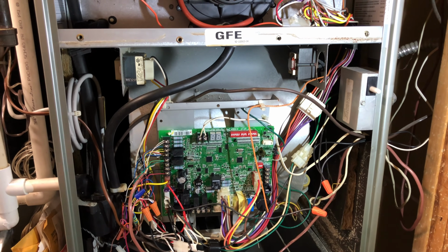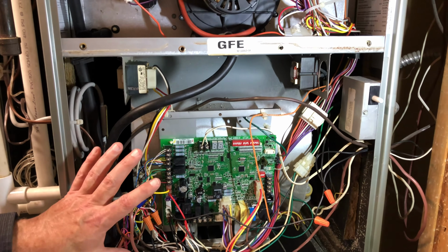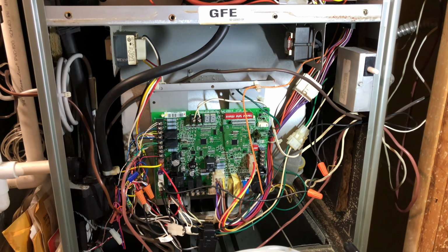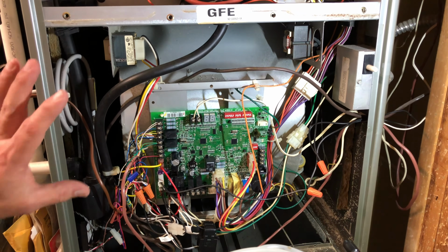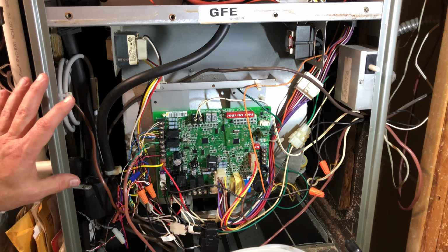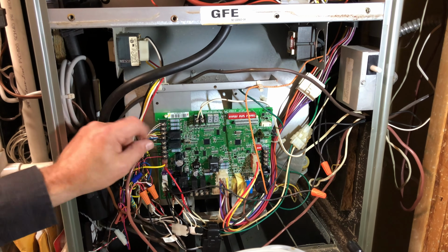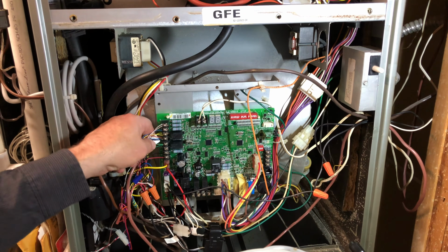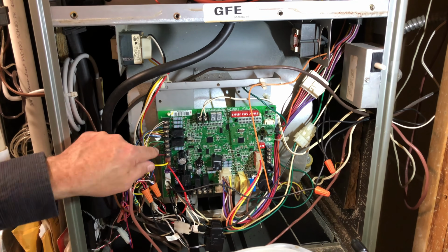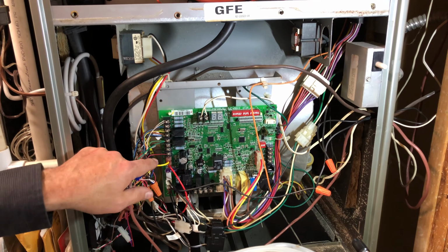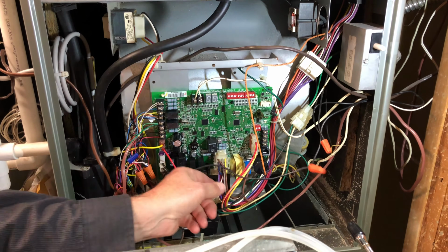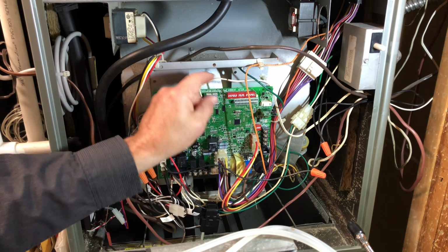But you really can't make a blower amperage reading with the door off, and plus it depressurizes your combustion air zone, has some other issues. So most of the readings we're going to make can be made on the top side of the furnace. I always go through and just tug on my thermostat wires, make sure everything's snug on the stat wires. Everything looks good there. You know, circuit board, Molex plugs, just make sure things are tight.